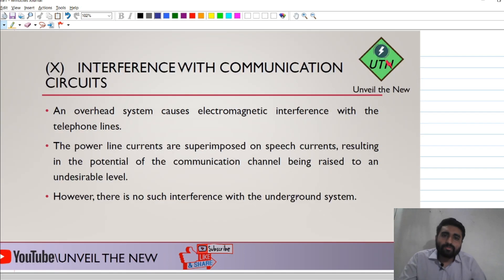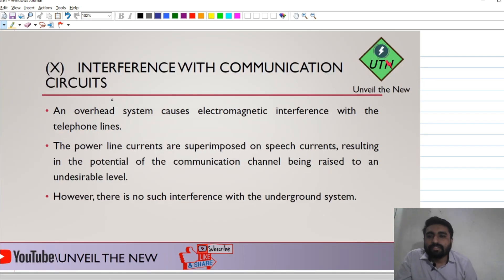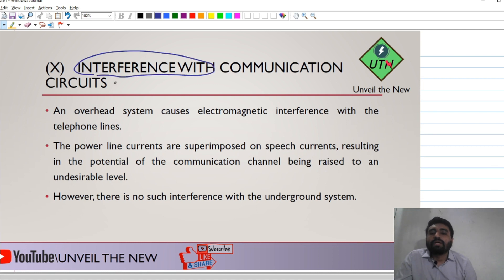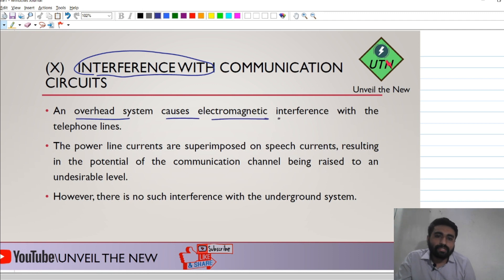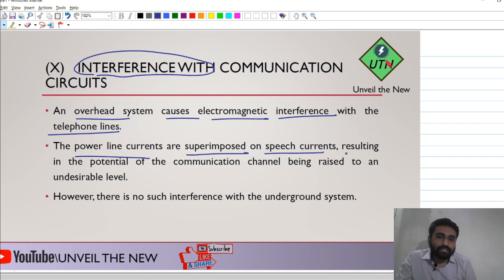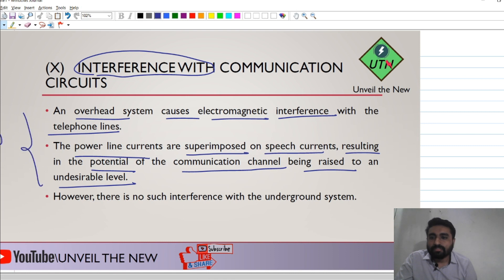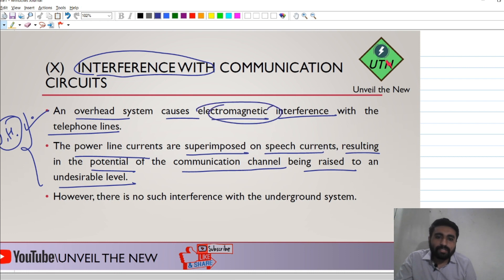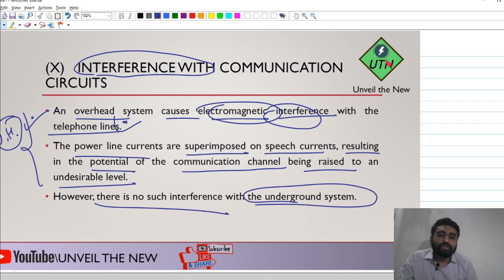The final parameter is interference. The overhead system causes electromagnetic interference with telephone lines, and power line currents are superimposed on signals, raising the communication channel potential to an undesired level. The overhead system is not quite suitable because of this electromagnetic interference. However, no such interference is observed in the case of the underground system, so underground system is the clear winner here.